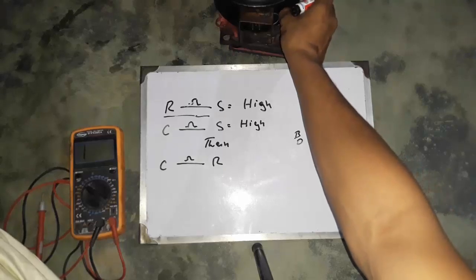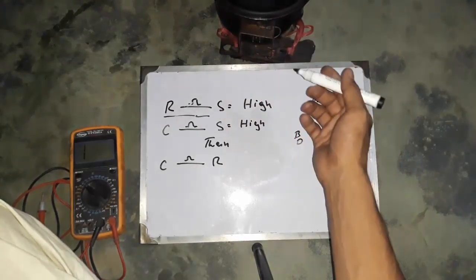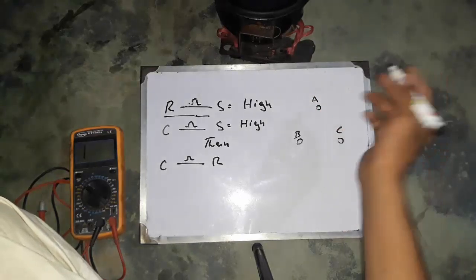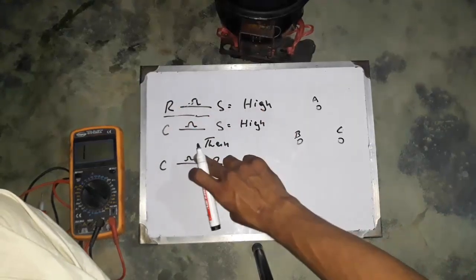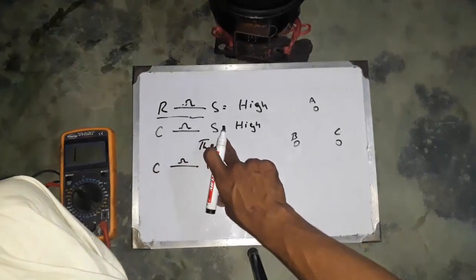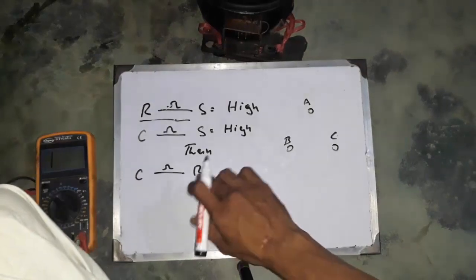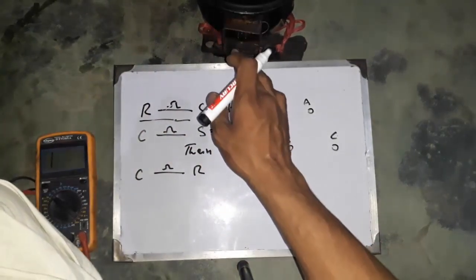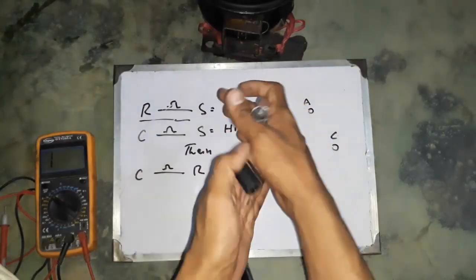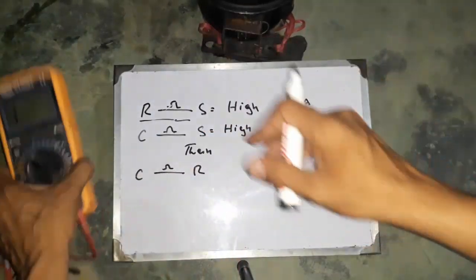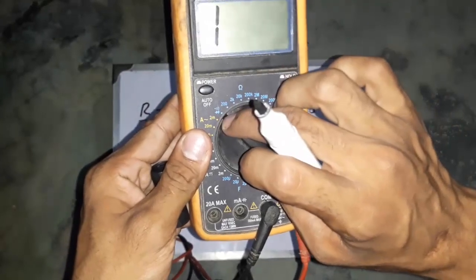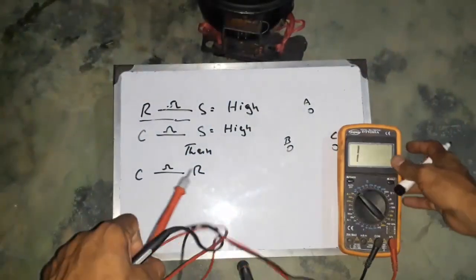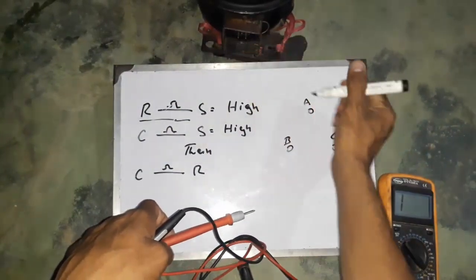Here I have a refrigerator compressor and I don't know about the terminals — which one is common, which is start, and which is run. We follow a simple formula: the resistance between start and run will be the highest, and the resistance between common and start will be higher than the resistance between common and run. I'll use a multimeter on the ohm testing or diode/buzzer option. I have three terminals which I've named A, B, and C.